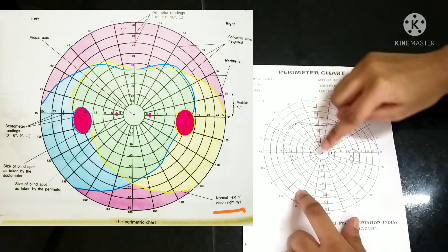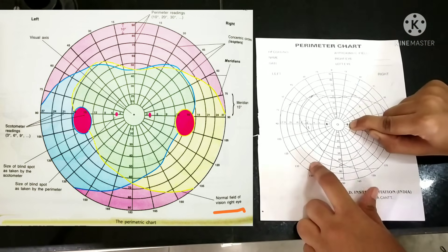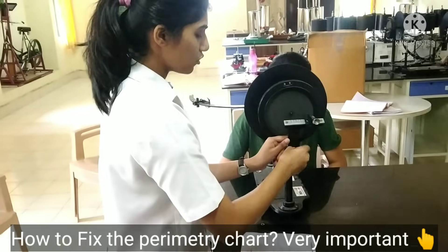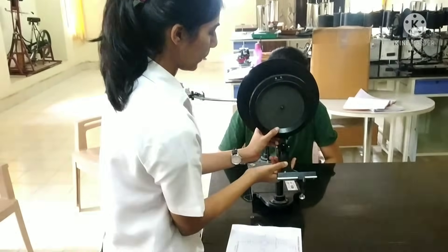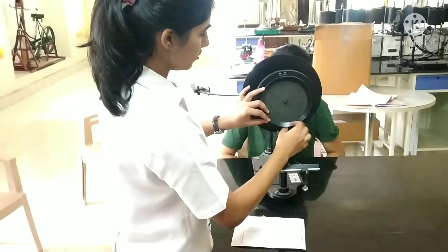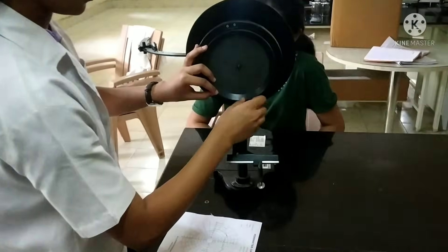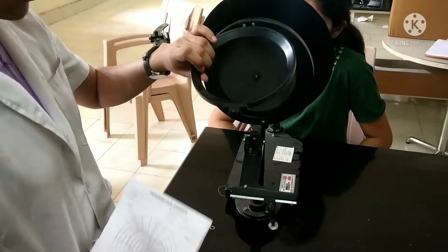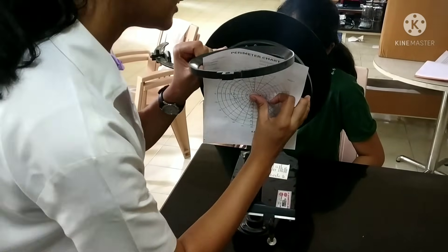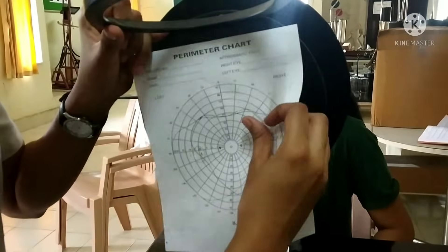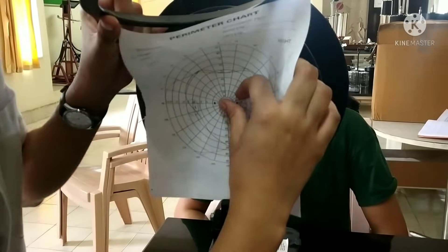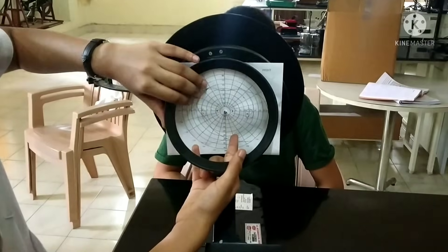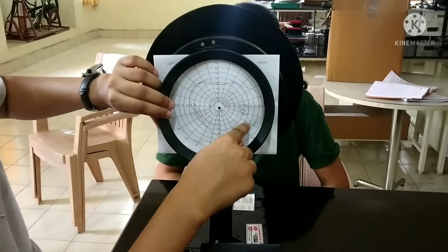The radii are known as meridians, placed at an interval of 15 degrees. The small dots visible on the chart represent the blind spot. To fix the perimetry chart, we remove the screws first, then pin the perimetry chart centered on the sharp point. Now we have fixed the perimetry chart.